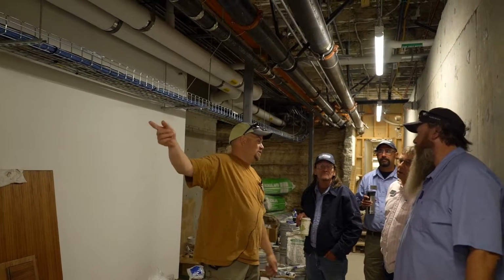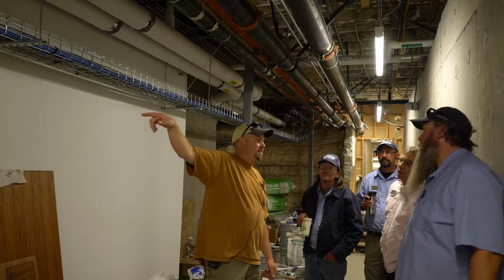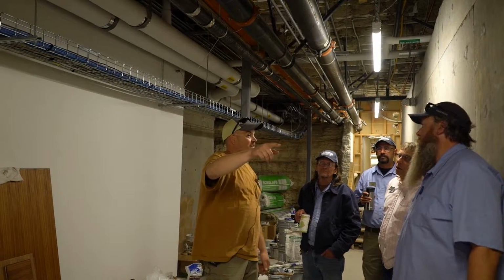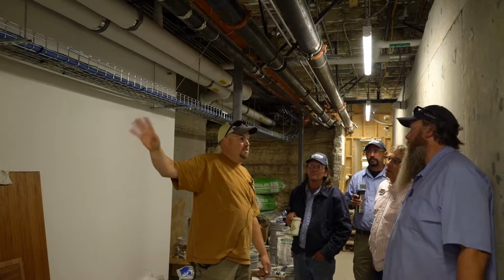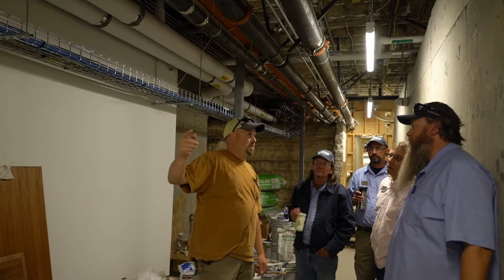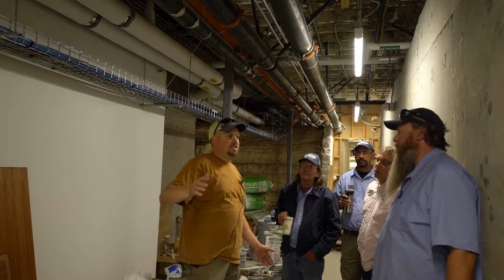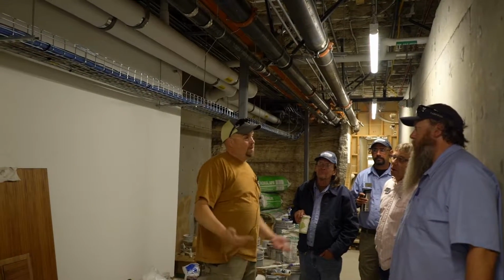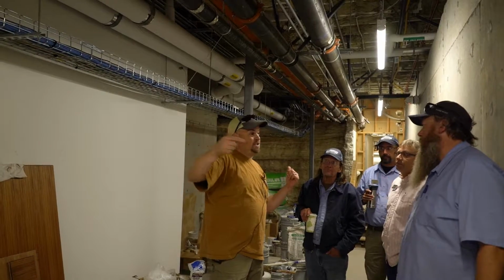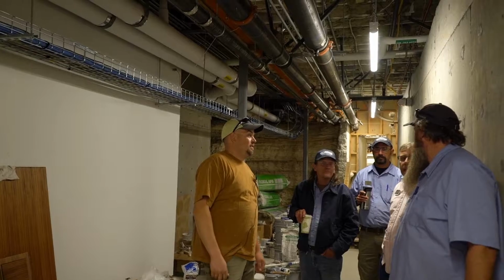Right. And what I was noticing is you have another recirc tied into your hotel recirc line down there. And there's a lot of back pressure, because when I tried to tie onto that recirc line and take that cap off after I shut off the hotel valve, I still had a ton of pressure. It was coming from, I think it said the accounting bathrooms, which were tied into that too with no check valve, no circuit setter. So that might be part of where your heating problem is coming from on the hotel side, because you got back pressure, with no circuit setters, no nothing tied onto it. That's what we're looking at right now.